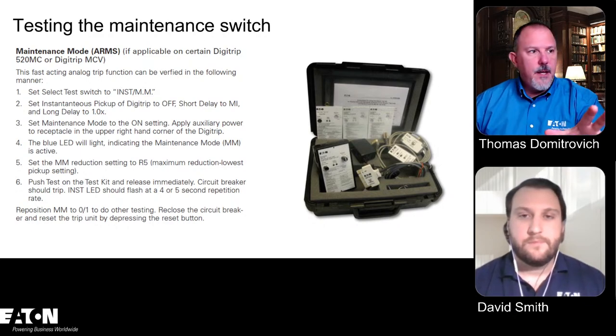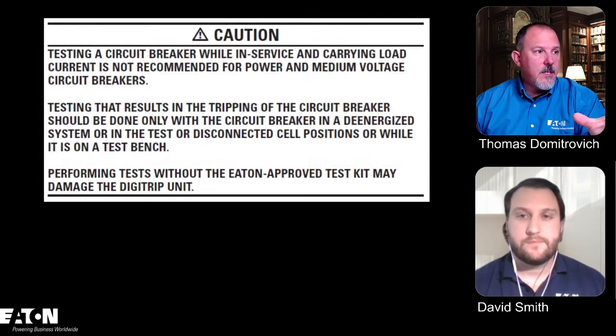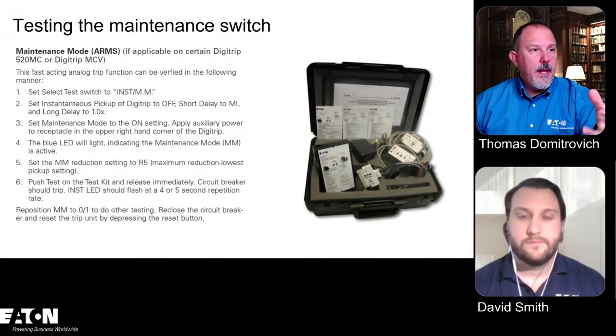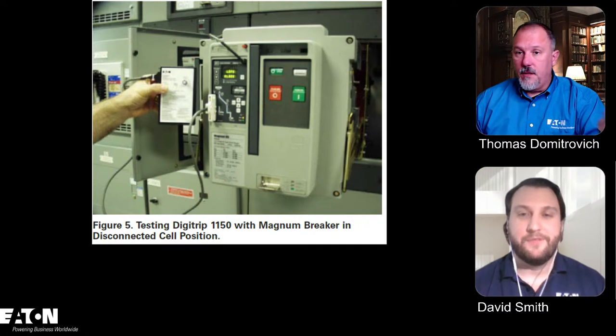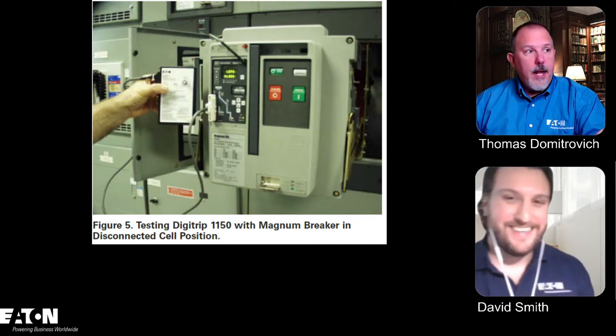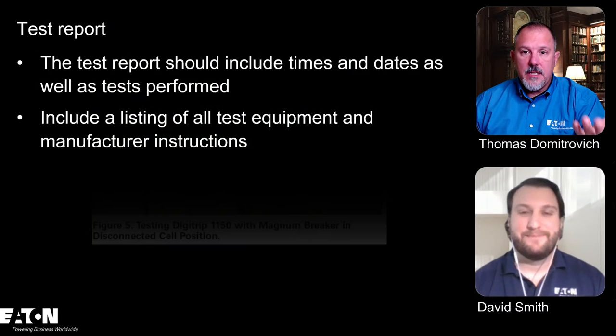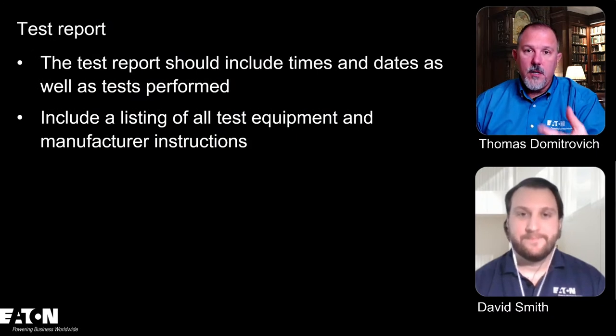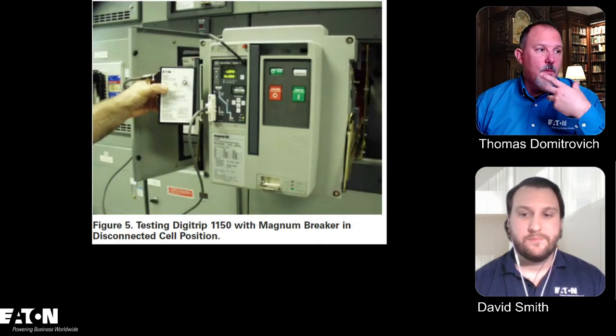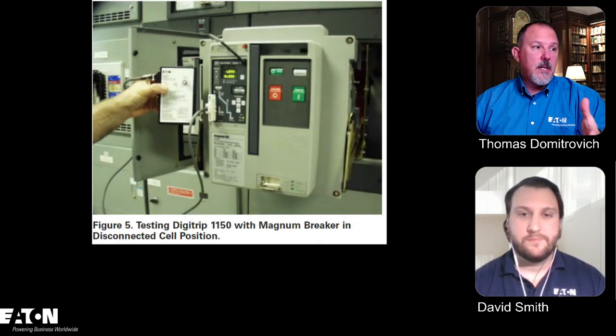We have a kit, and this is what it looks like. You get this briefcase that has basically what you need. You plug it into the front of the circuit breaker, and you have a test button there. You press that test button, and it gets you a test report. You can download the test report. It'll open that device, and it will run for the arc reduction maintenance switch.